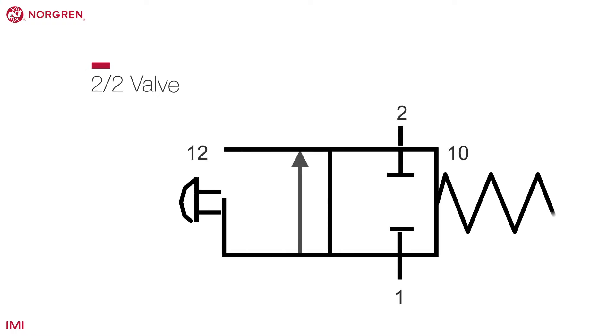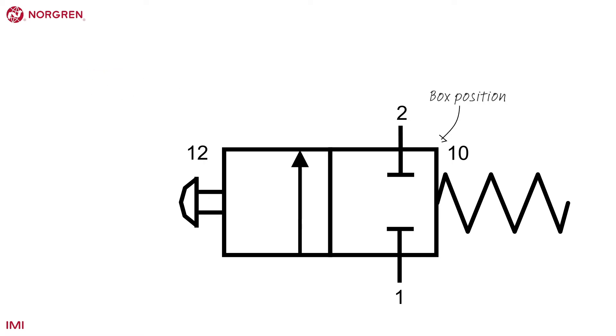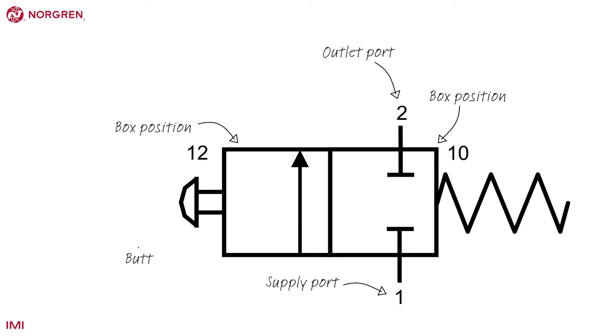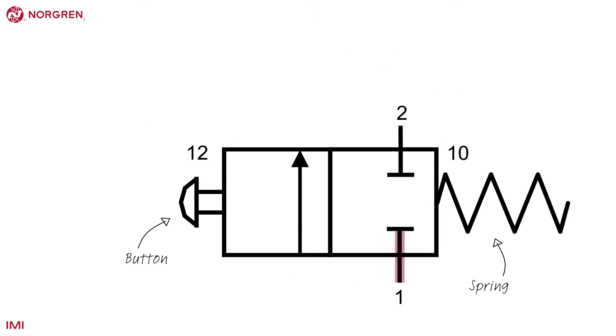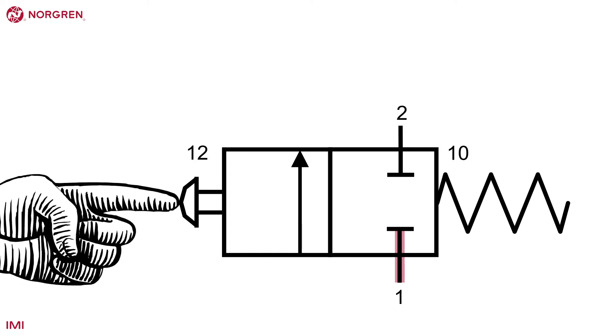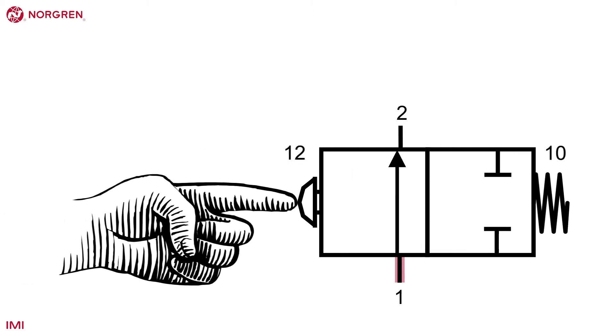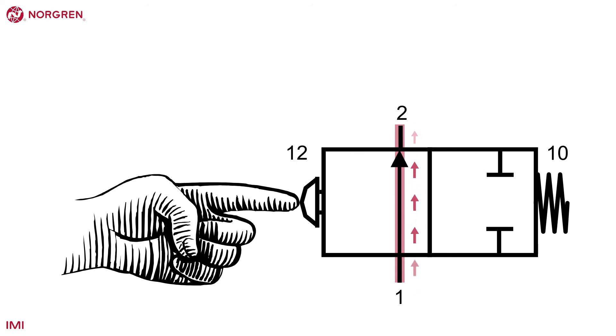This is the symbol for a 2-2 valve that you may see on a system diagram. Each box represents a position and each number represents a port. The illustration also includes a button and a spring. In position 1, no air will flow — often called the zero position and illustrated with a T-shape. In position 2, air flows from port 1 to port 2, as illustrated with an arrow.